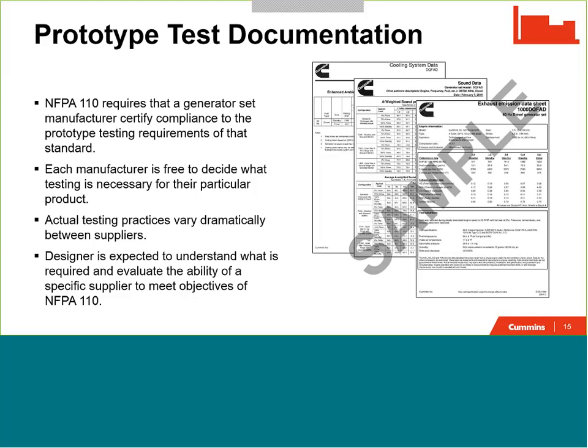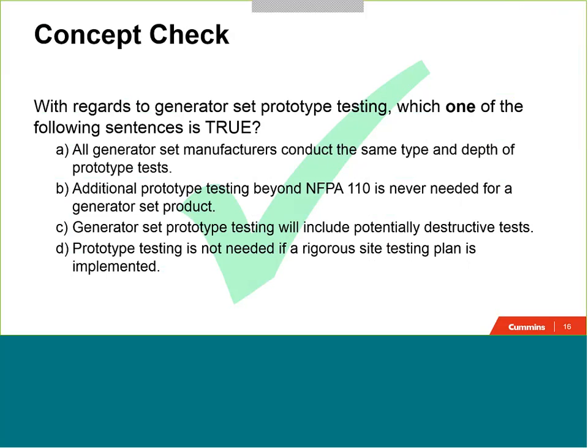So with that, we are going to move quickly into a concept check here, and I'm going to go ahead and read through this, and we'll give you an opportunity to respond. With regards to generator set prototype testing, which one of the following sentences is true? A: All generator set manufacturers conduct the same type and depth of prototype tests. B: Additional prototype testing beyond NFPA 110 is never needed for a generator set product. C: Generator set prototype testing will include potentially destructive tests, or D: prototype testing is not needed if a rigorous site testing plan is implemented.